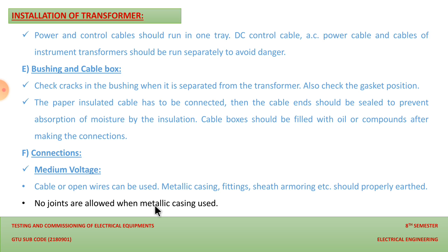Now, in the installation of the transformer, the next point: the first was for the medium voltage, and this is for the high voltage. For high voltage, paper insulated lead sheath and armored aluminum cable or other suitable cable should be used. When the connection is on the high voltage side, it is to be done using the insulated cable.